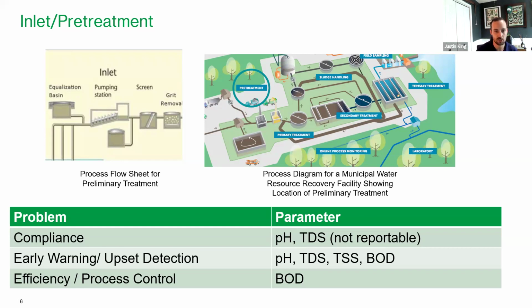So what kind of online instrumentation is most effective in the very beginning steps of a wastewater treatment plant? Well, that is typically pH and TDS, as you can see here. But we also can measure TSS and BOD as well as ammonia. Monitoring the pH, TDS, and TSS can provide early signs of upset conditions. So if we have cases where there could be incoming chemical slugs that could wipe out the bugs in the activated or primary treatment stages, we can mitigate that and divert that water flow if we have online instrumentation constantly monitoring the inlet of the plant.